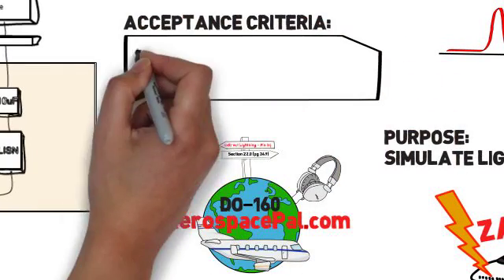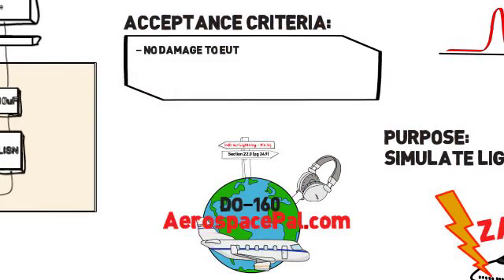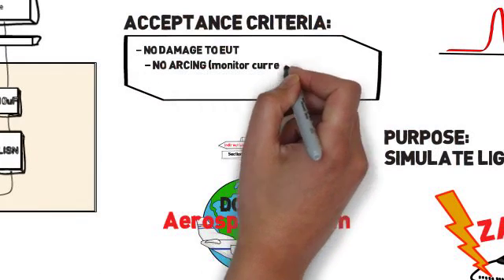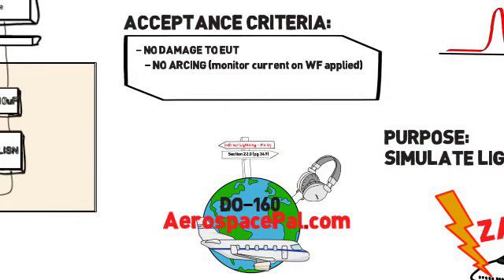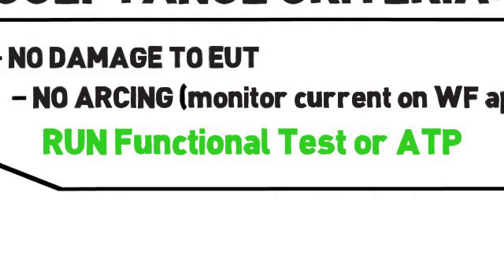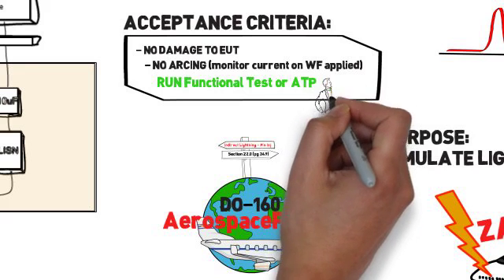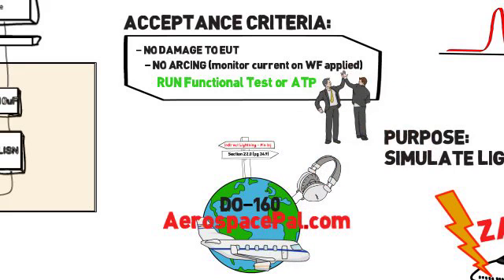Ensure that there's no arcing during the test by monitoring the current seen by the applied waveform. Once the waveforms have been applied, run a functional test on the spot or an ATP to ensure your EUT is operational and has not been affected by the test. And that's one half of DO-160 section 22 pin injection.